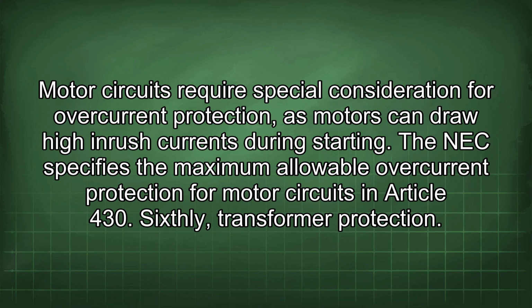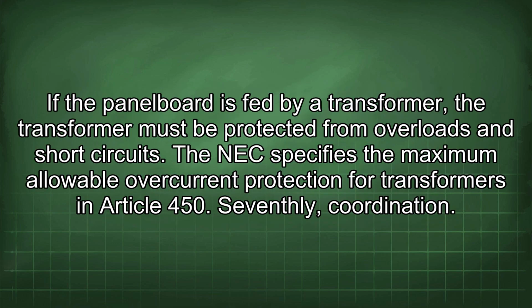Sixthly, transformer protection. If the panel board is fed by a transformer, the transformer must be protected from overloads and short circuits. The NEC specifies the maximum allowable overcurrent protection for transformers in Article 450.